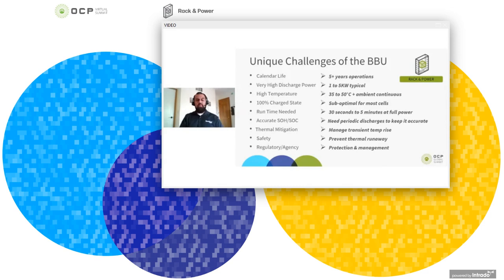Another big issue with BBUs is the ability to have accurate state of charge and state of health data. Most fuel gauges require discharge and charge cycles to stay accurate. Since BBUs are not discharged often, the fuel gauge can become stale, so we need to find ways to periodically do partial discharges while still being ready to handle a backup event.